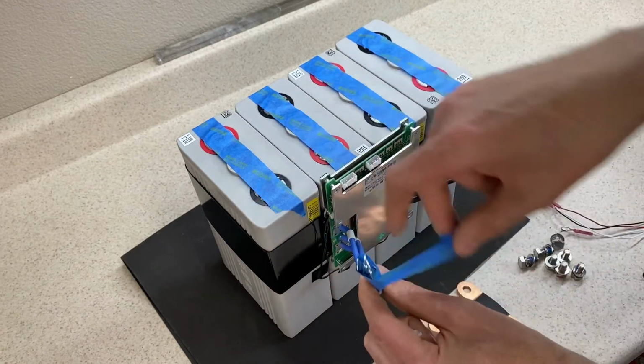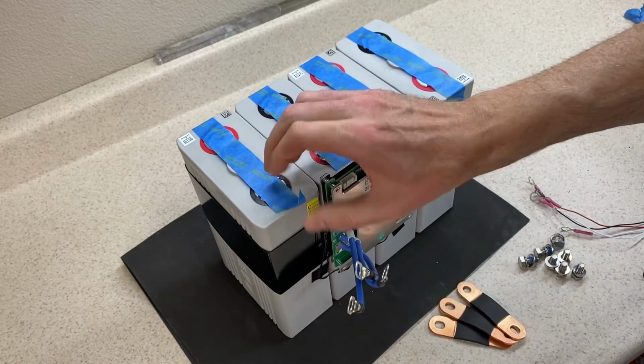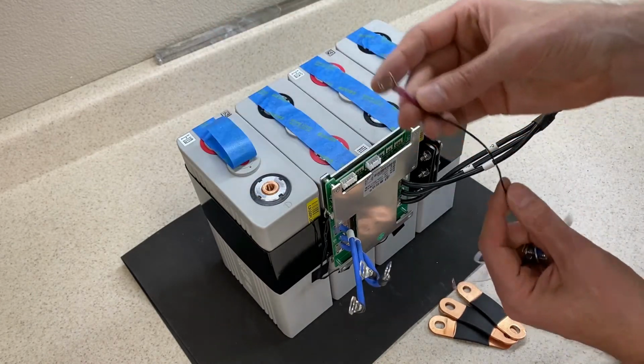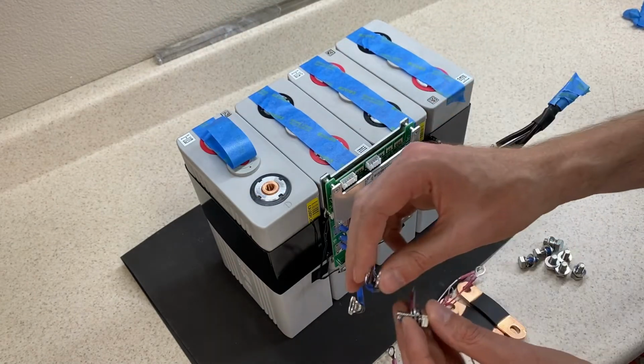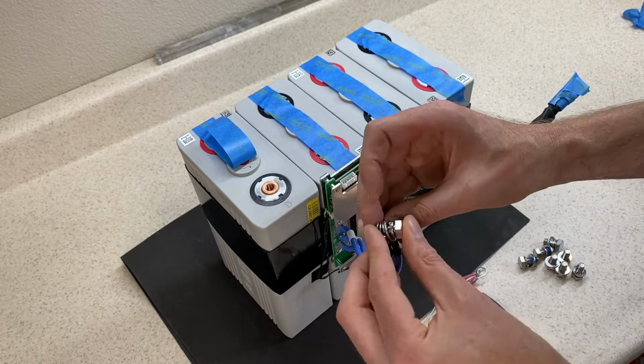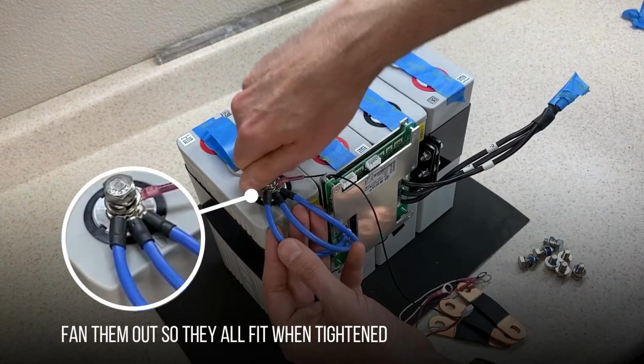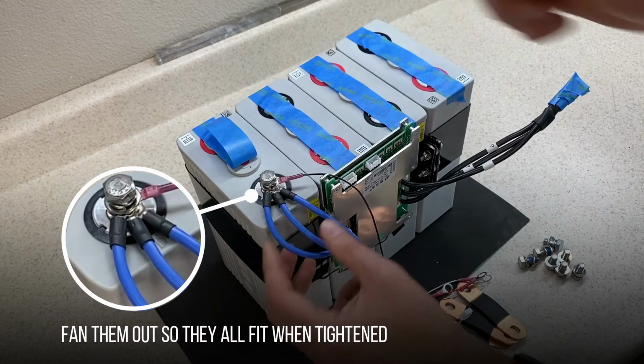We'll start with the main battery negative, only exposing the terminals that we're working with for safety. Slip the black balance lead and all 3 of those B- leads onto a bolt, and then thread it into the cell 1 negative terminal, making sure that balance lead's on the top of the stack.